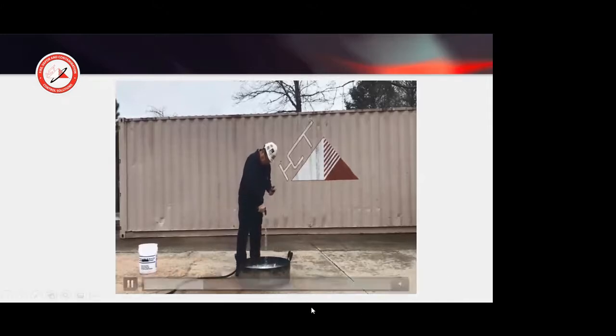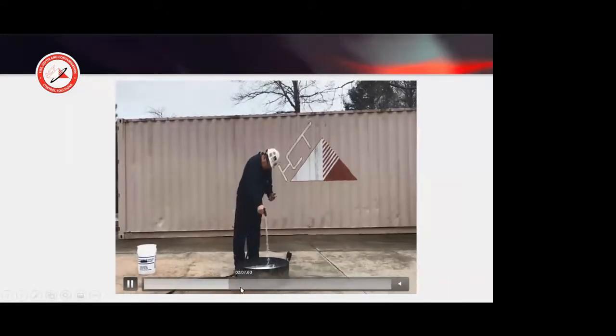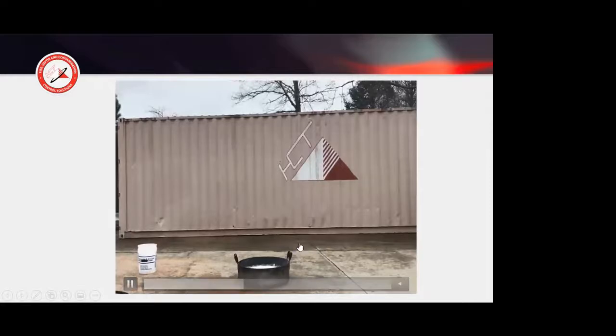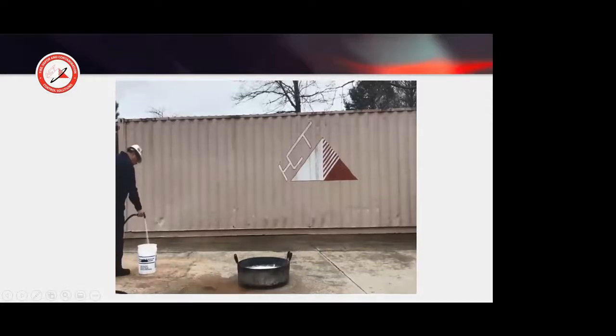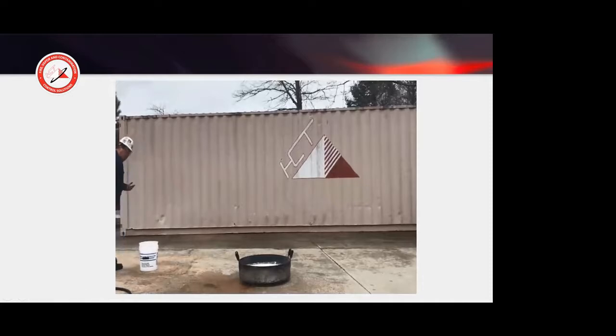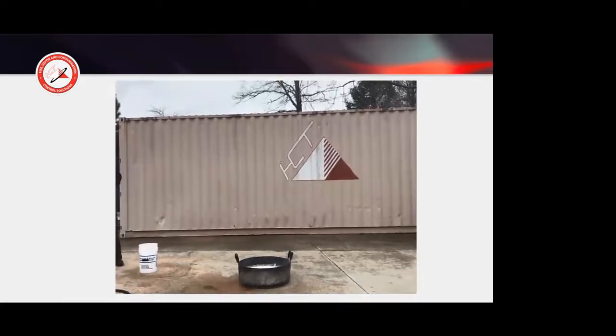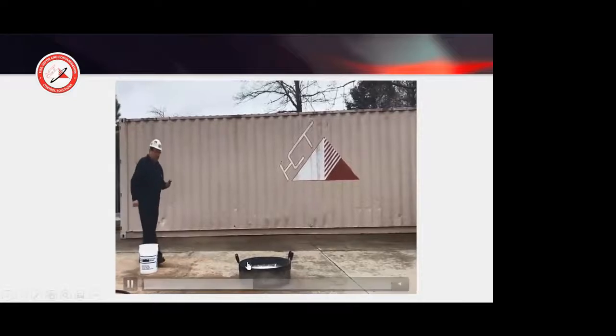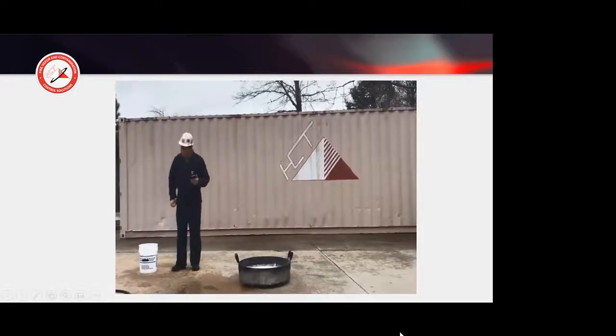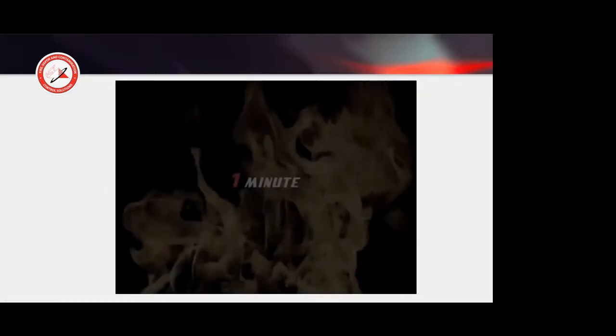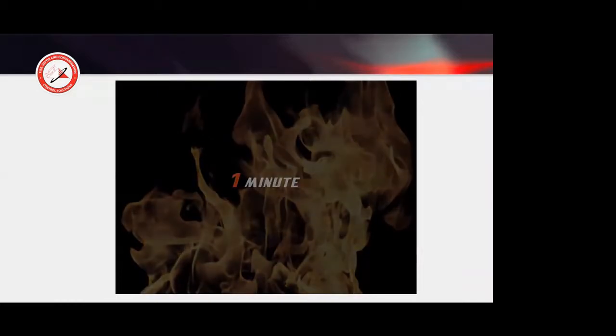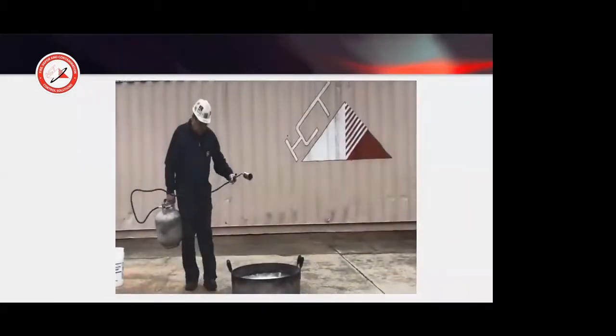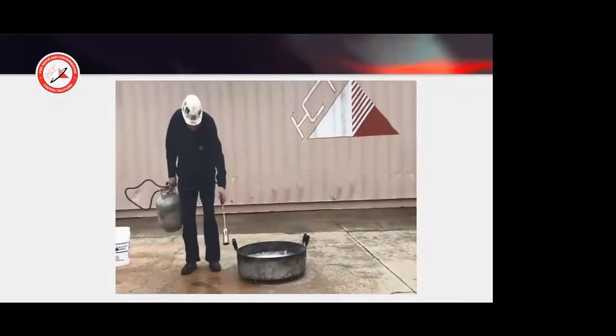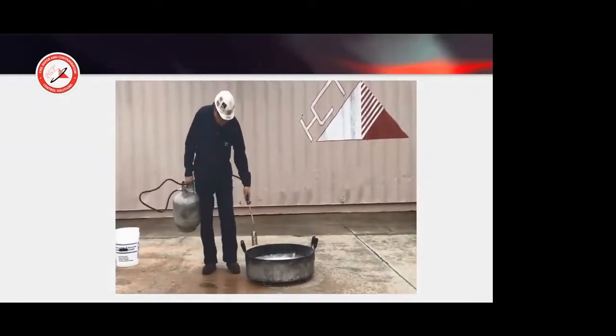So I'm going to try to speed ahead here just a little bit. So we've taken 1 minute, we've mixed in the water. Now the test says wait for 1 minute, and then we're going to put a torch to the top of this surface of the pan here, to the complete surface. And we cannot have ignition. If we look at the pan, we don't see any foam bubbles. If this was plain water, the fuel would float up on the top and it would light instantaneously. If this were a wetting agent, again, the fuel would float up on the top and it would light instantaneously.